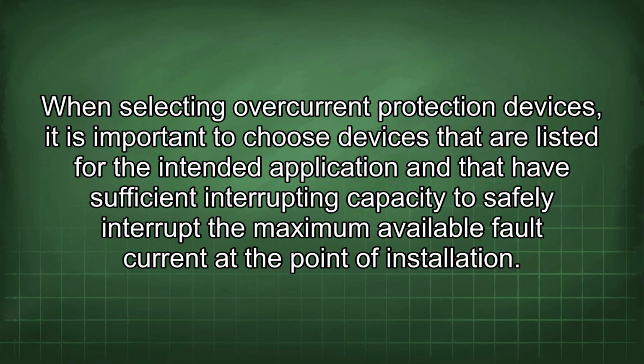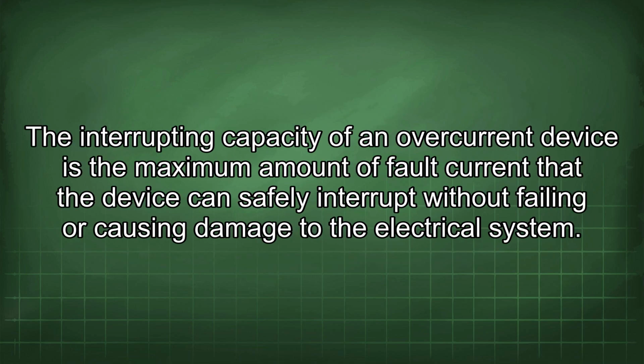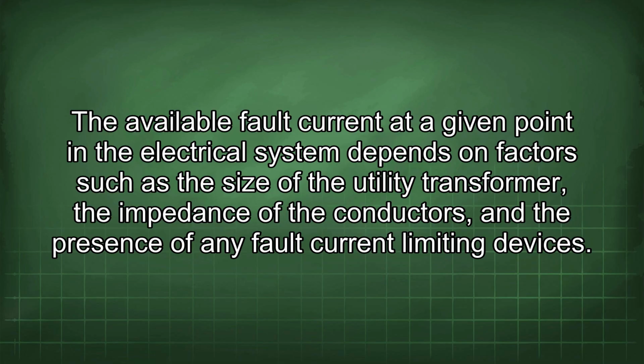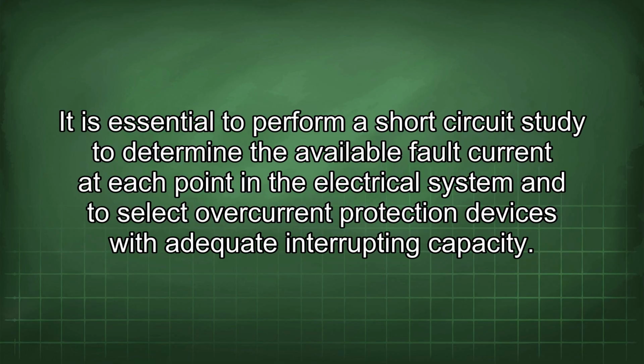When selecting overcurrent protection devices, it is important to choose devices that are listed for the intended application and that have sufficient interrupting capacity to safely interrupt the maximum available fault current at the point of installation. The interrupting capacity of an overcurrent device is the maximum amount of fault current that the device can safely interrupt without failing or causing damage to the electrical system. The available fault current at a given point in the electrical system depends on factors such as the size of the utility transformer, the impedance of the conductors, and the presence of any fault current limiting devices. It is essential to perform a short circuit study to determine the available fault current at each point in the electrical system and to select overcurrent protection devices with adequate interrupting capacity.